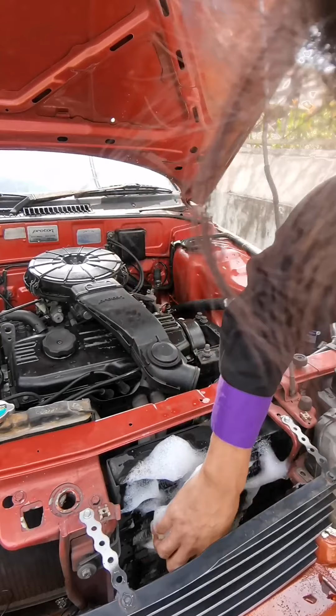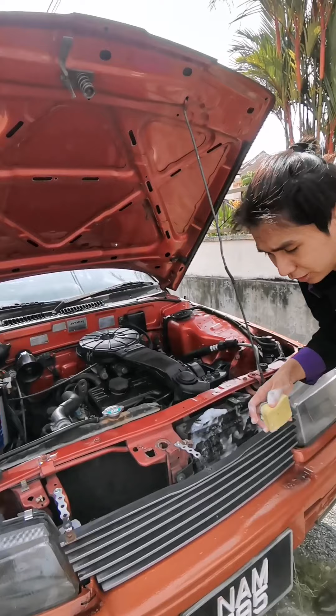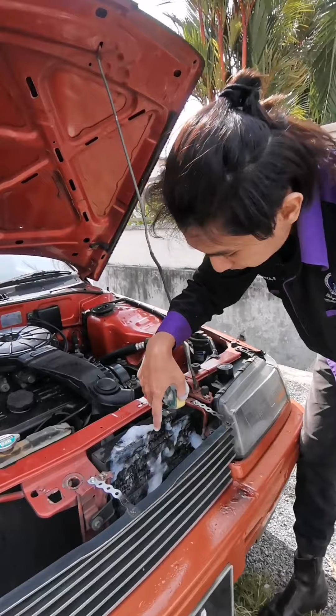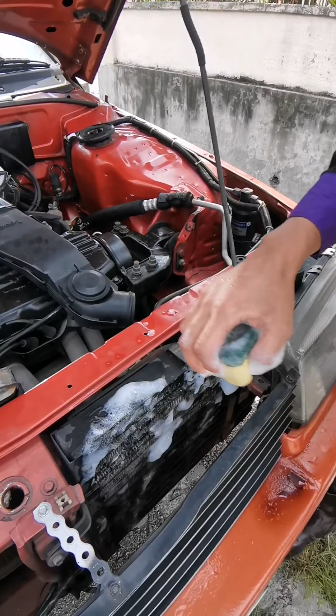Okay, and then the air conditioning is on. The aircon is on. So when I apply the soap, monitor where the leak is. So, come here. There's no leak on the condenser. If there's a leak, bubbles will come up from the condenser.